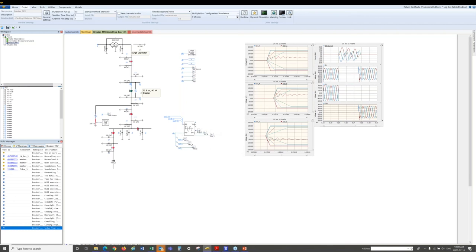And on this side, as I said earlier, you just plot the envelope with a particular actual TRV measurement. So both together, this is phase A, phase B, phase C. I ran the first simulation already, and you see here, if I zoom a little bit more, the TRV is cutting all the innermost 100, 60, 30, 10, all the curves. So this is a clear violation of TRV in this particular case.